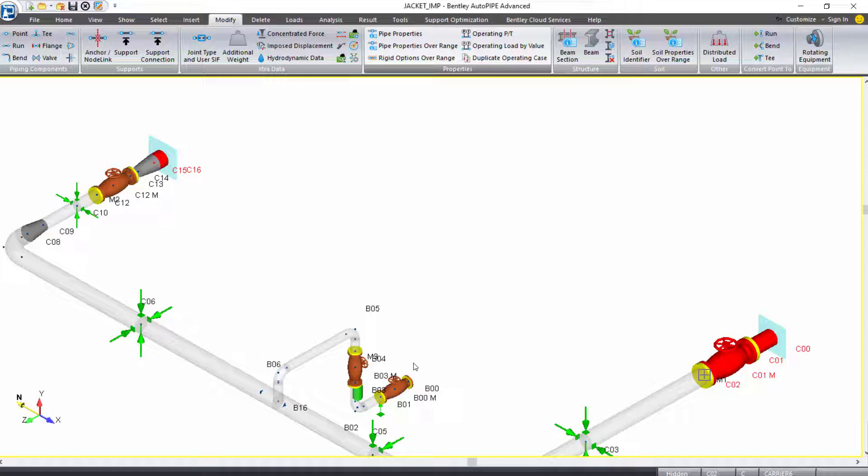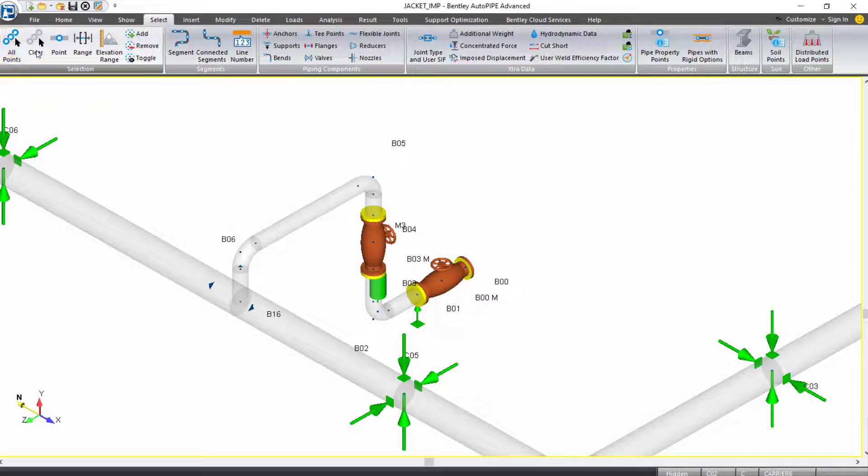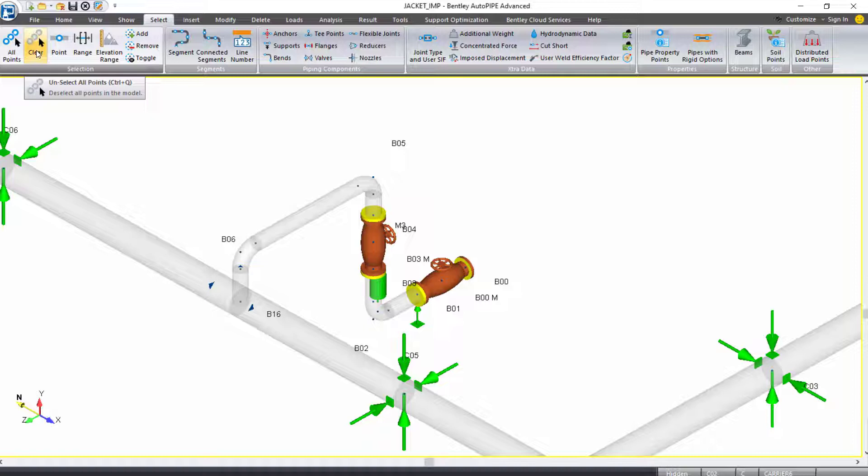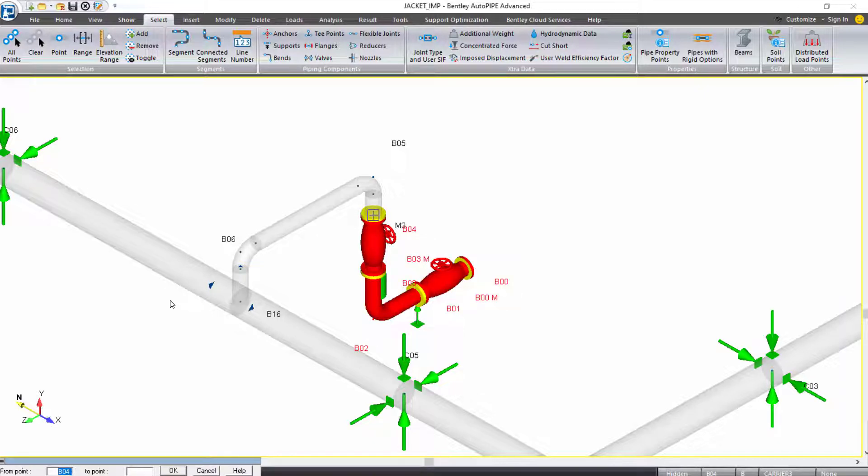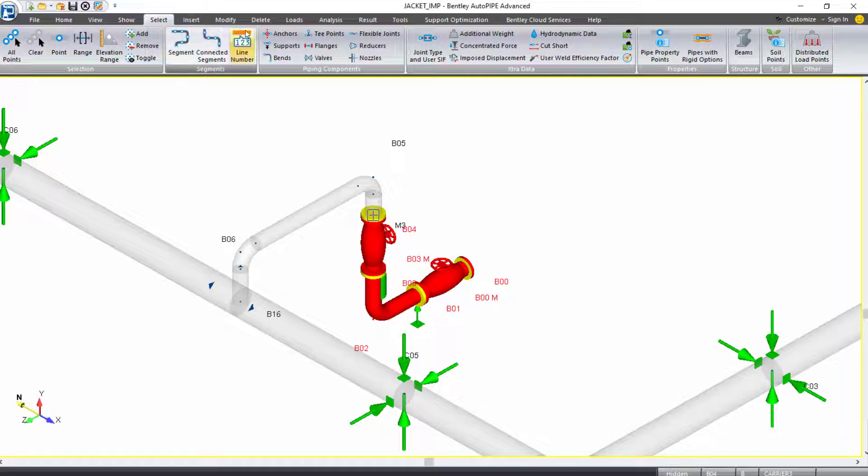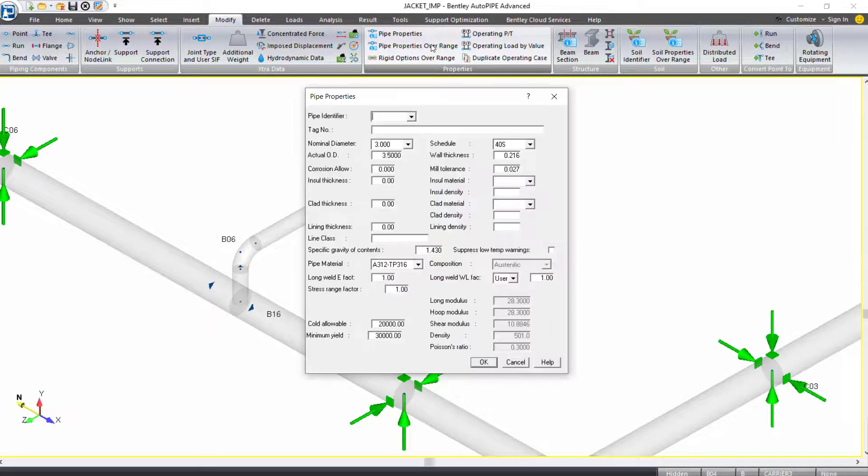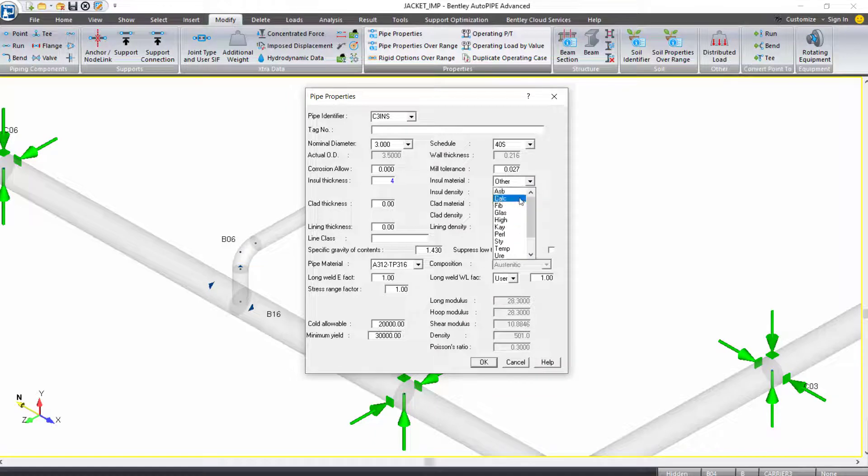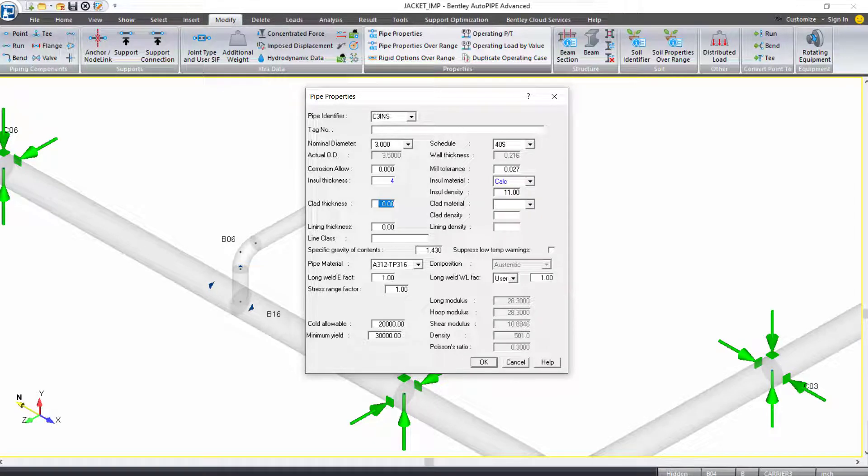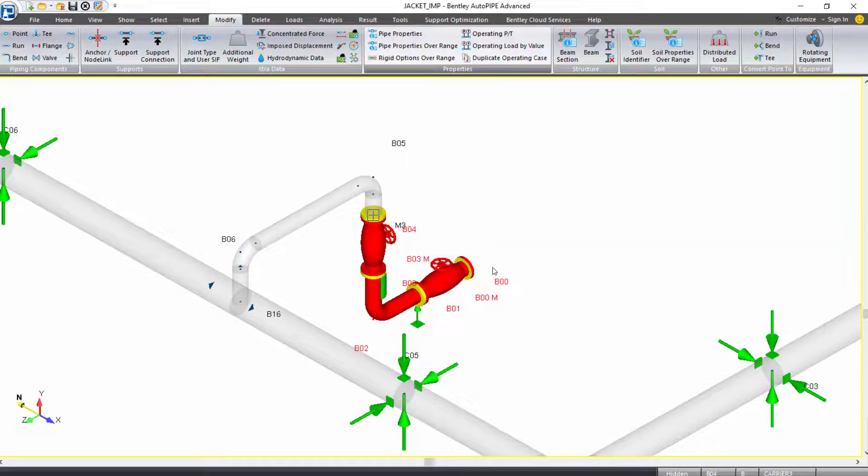Lastly, I want to do the branch line of the carrier pipe that's outside of the jacket. This will be from B0 to B4. First things first, I want to come to my select ribbon tab and clear my selection. Then I will select the range. I will type in B00 to B04 and press tab. That selection is made, and it's the only selection here, so I can click OK. I'll come up to the modify ribbon tab. Modify pipe properties over range. This is a three inch carrier pipe, so I'll name it C3INS. Tab down to my insulation thickness. We'll keep the same four inches of calcium silicate. And we can click OK and OK.